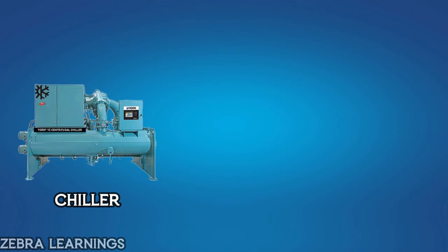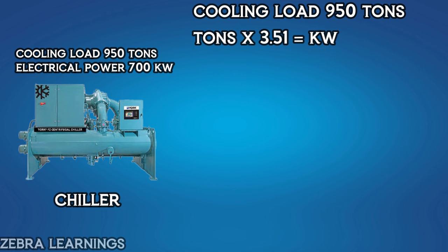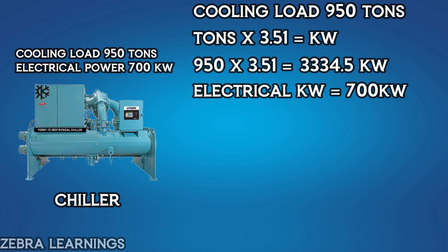Let's assume a chiller is running at a cooling load of 950 tons. We can convert this to kilowatts. If we multiply the tons value by 3.51, we will get the kilowatt value. 950 multiplied by 3.51 equals 3334.5 kilowatts. The electrical kilowatt of the chiller is 700.